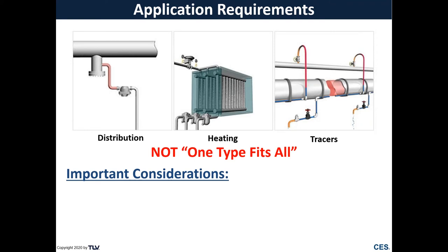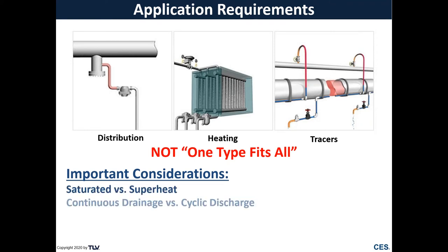So there's a lot of important considerations, like, is my steam superheated or saturated? Do I need continuous drainage, or can I tolerate a cyclic discharge steam trap? Can I tolerate condensate backup and subcooling, or do I need to have immediate condensate drainage from that steam trap? And these are just a few of them, along with air venting.